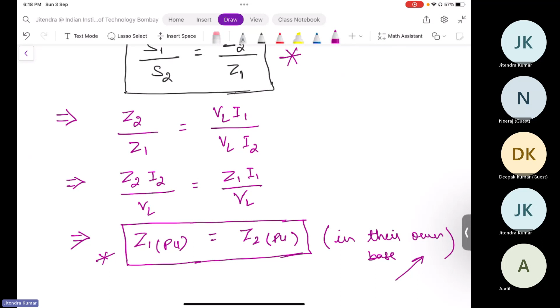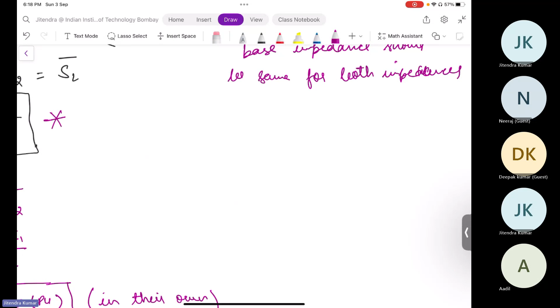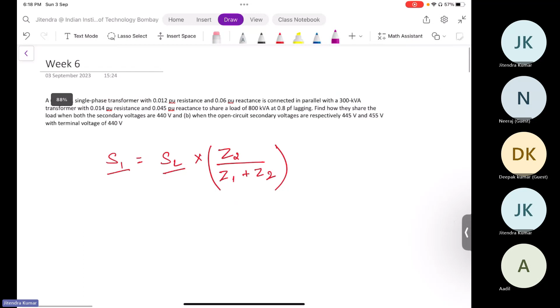Okay. Now, I would like to extend this theory a bit further. What happens when any transformer is overloaded? If their loadings have to be in the ratio of their respective kVA ratings, it means their per unit impedances should be equal. But what happens if they are not equal? What happens if transformer 1 has a lesser kVA rating compared to transformer 2? That is the actual scenario in this problem.